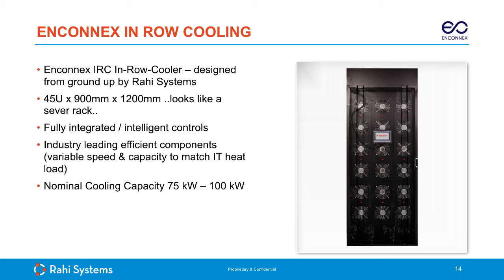Let's back up just a little bit on the intro for the Enconnex row-based. Big picture wise, we've been talking about the trends that I've touched on around high power density and also variable density of IT equipment. Those are key challenges. They create conditions for traditional data center cooling that it wasn't really intended for. It was more room-based. And the resulting cooling system designs tend to be either oversized or inefficient, or the controls can be not fine-tuned, a little bit unpredictable. So row-based cooling, such as the Enconnex IRC, has been developed to address these problems. So let's go to the next slide.